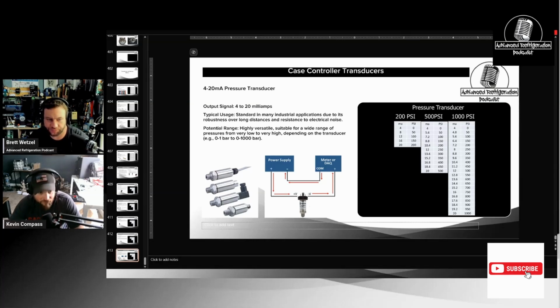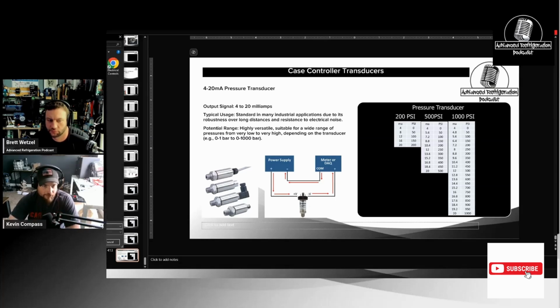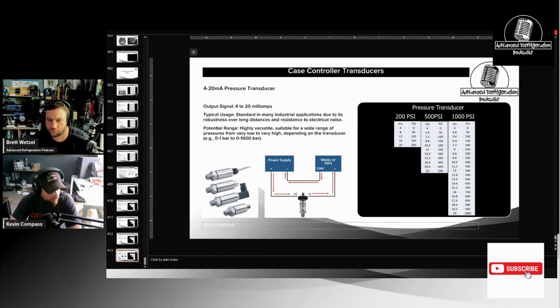Yeah, so like a 179, 178, one of those, they're all fused. So if you accidentally do that, I always check it first with my meter leads. I put them in the normal spot where it works for ohms, and then I'll stick them in the other spots where the milliamps are, so I can make sure the fuse is closed. Because you don't want to condemn something that's not bad because you blew the fuse 8 months ago and didn't remember.